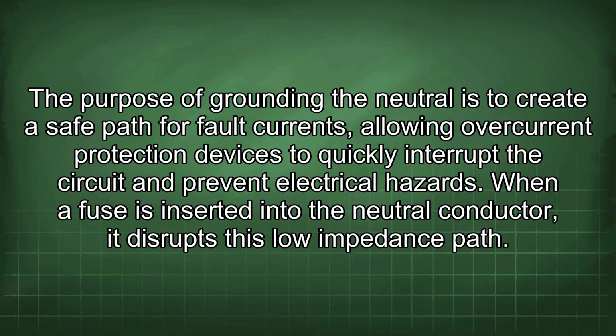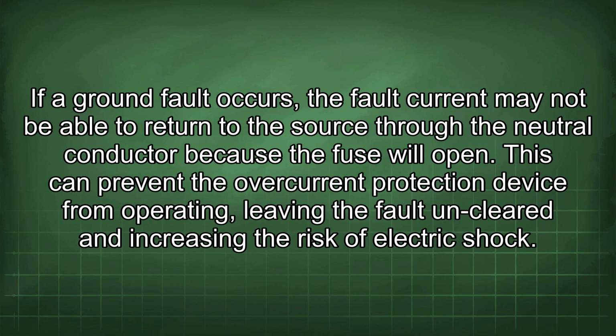When a fuse is inserted into the neutral conductor, it disrupts this low impedance path. If a ground fault occurs, the fault current may not be able to return to the source through the neutral conductor because the fuse will open. This can prevent the overcurrent protection device from operating, leaving the fault uncleared and increasing the risk of electric shock.